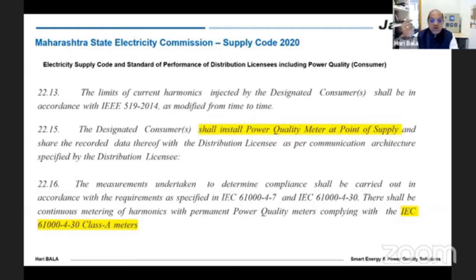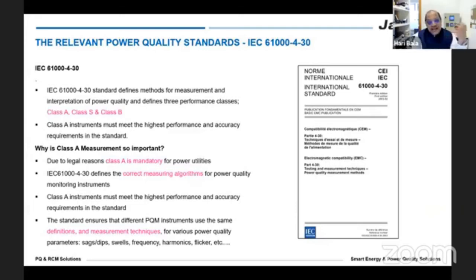The measurement undertaken to determine compliance shall be carried out in accordance with IEC 61000-4-7 and IEC 61000-4-30. So this is a very clear mandate coming from the supply code of MERC as well. Now, I wanted to slightly touch upon what 61000-4-30 is. It is the standard which defines how the measurement of power quality should be done. It clearly defines the algorithms: how the sample should be taken, how the measurement should be done, how the calculation should be done in the meter, and then how the data should be presented.